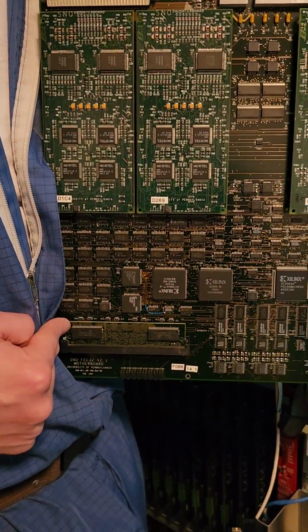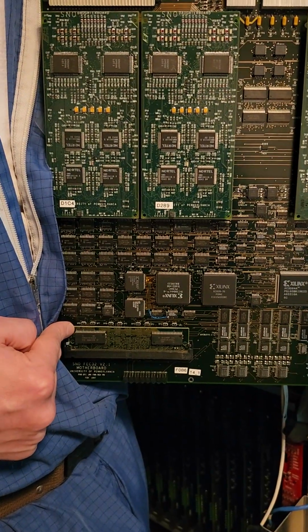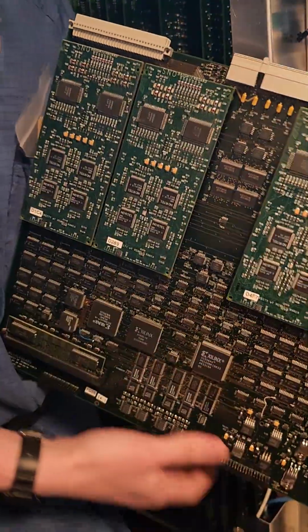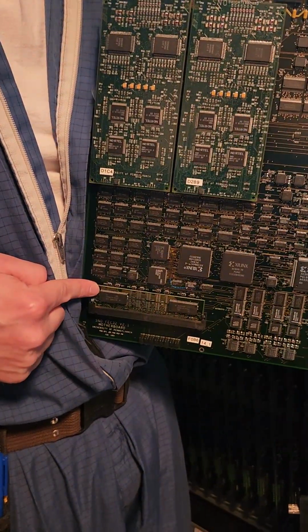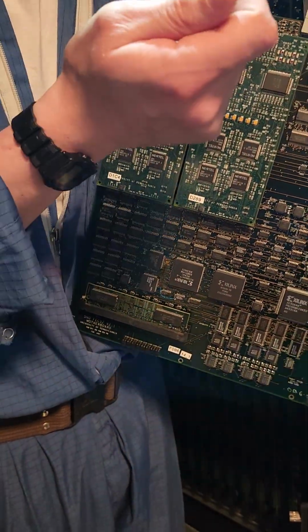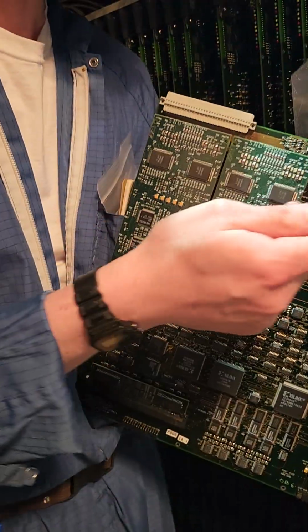That is able to hold 1 million and a bit PMT pulses, because the amount of data in that PMT pulse is small, only 96 bytes. So again, it is entirely possible to overload this because we just use it as a first in, first out array. So you write a pulse in, and then it just queues up.